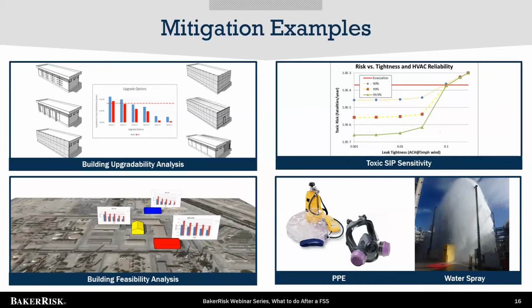For the water spray, this is important in the design of new buildings as well. Not for buildings, but a water spray system is a post-release measure to limit the impact of releases at the facility. Water spray systems include things like water curtains, fixed water monitors, portable water cannons, and sprinklers. The picture on the right is an example of a water curtain. But directing water spray through a gas cloud has several effects, and the interaction between vapor cloud releases, air, and water droplets can be a complicated scenario to model and predict. However, there's extensive research that's been conducted around water sprays to mitigate dense clouds like hydrogen fluoride, chlorine, and ammonia, for example.